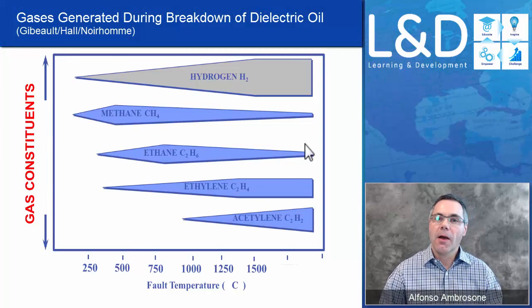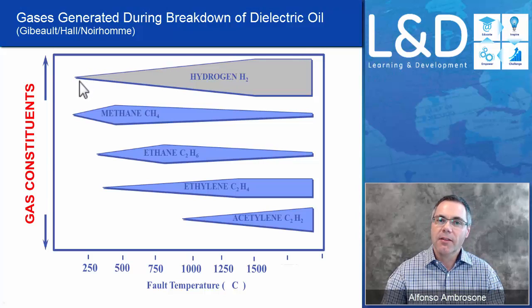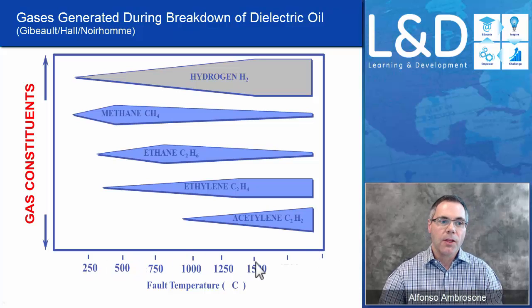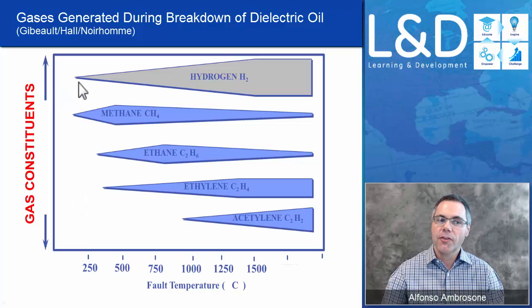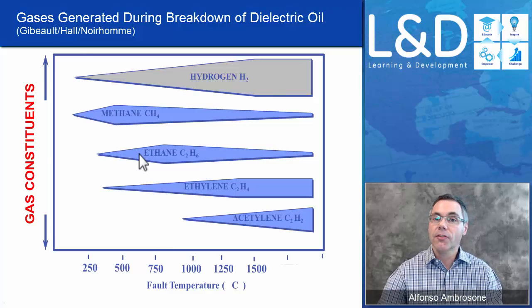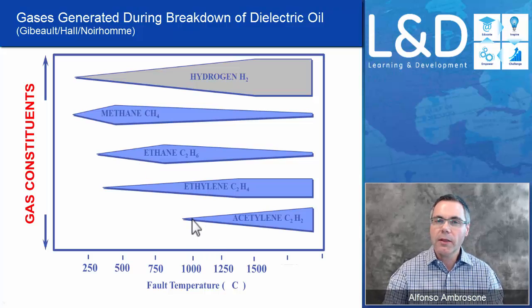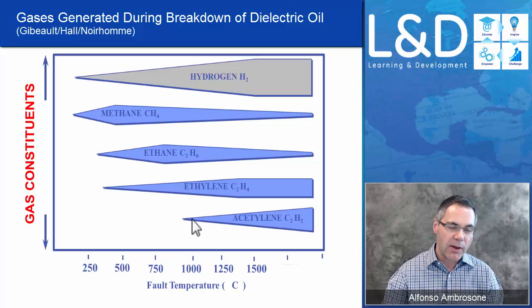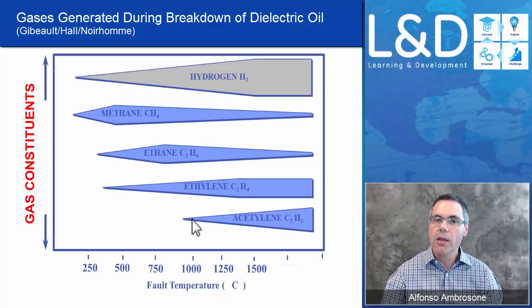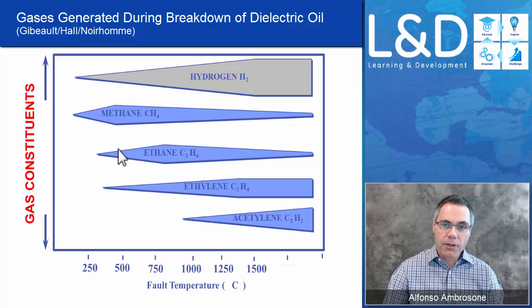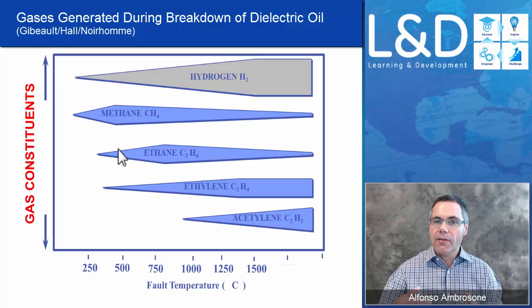This chart shows how that occurs. Hydrogen is a gas that develops at very low temperatures. The x-axis represents the temperature of the fault within the main tank. At very low temperatures, hydrogen is produced, and as the temperature of the fault increases, hydrogen increases. The development of other gases also starts to appear. Acetylene only starts to appear in the oil at high temperatures — around 1,000 degrees — which is usually caused by arcing. So when you have arcing, you will have acetylene. Depending on the type and concentration of gases generated, you can start to understand what kind of breakdown is occurring in the main tank.